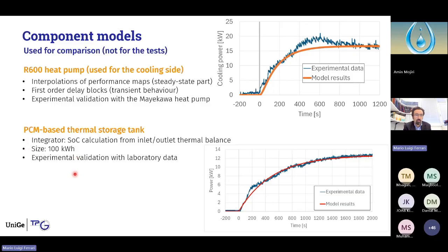The phase change material-based thermal energy storage tank has been modeled based on inlet-outlet thermal balances, and the size was 100 kilowatt hour, not very large in comparison with the other one, but it is the device available in our laboratory. Also in this case, we compared the model results with the experiments for the startup of a discharge phase, obtaining a good matching.